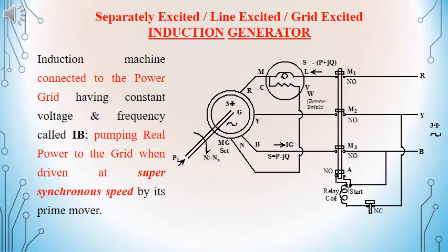First, we will be discussing the separately excited or line excited or grid excited induction generator. The induction machine is connected to a grid where we have a constant voltage and constant frequency system, and it is also called an infinite bus. The induction generator will be pumping the real power to this grid, and an induction machine will be operating as induction generator when it is driven at a speed above synchronous speed or at super synchronous speed.